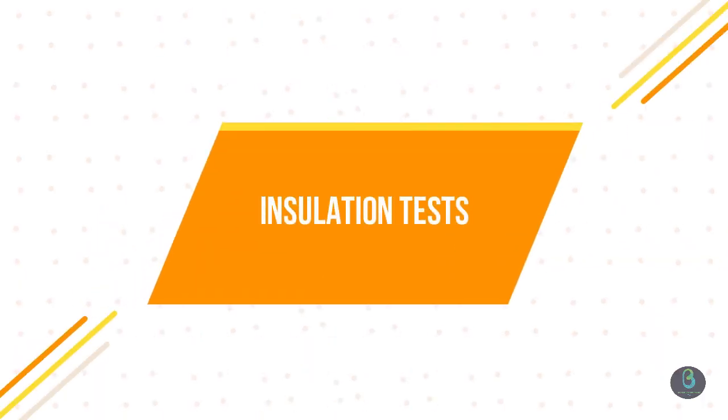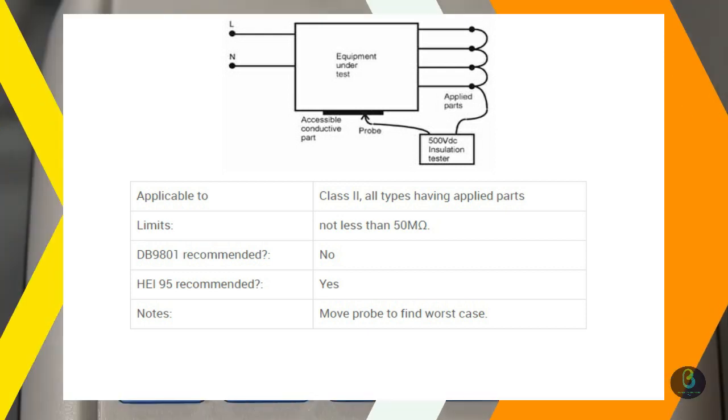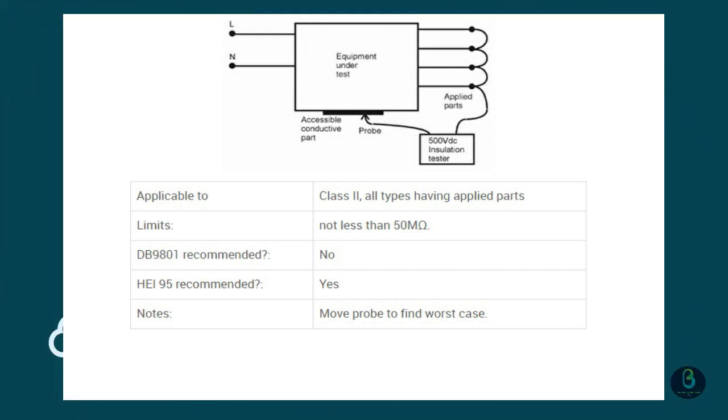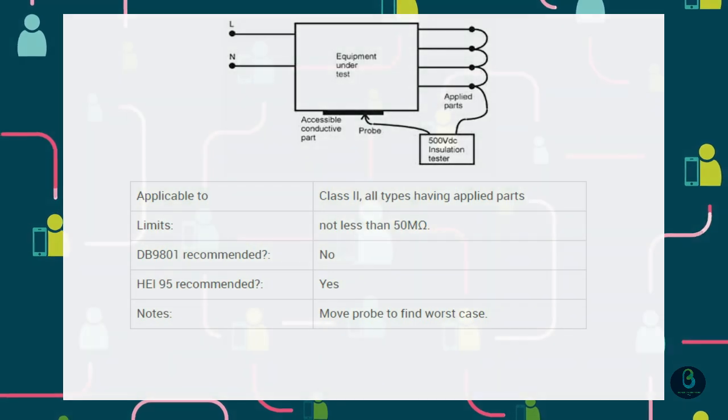Insulation Tests. IEC 60601-1 lays down specifications for electrical separation of parts of medical electrical equipment, compliance to which is essentially verified by inspection and measurement of leakage currents. Further tests on insulations are detailed under Dielectric Strength.